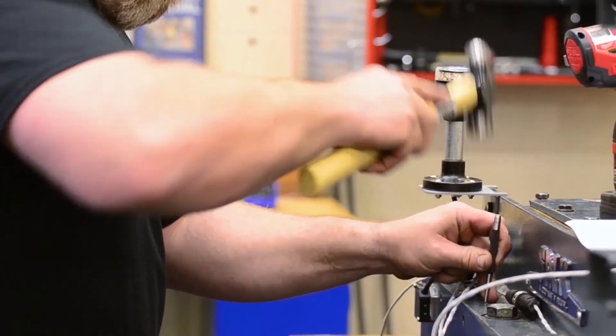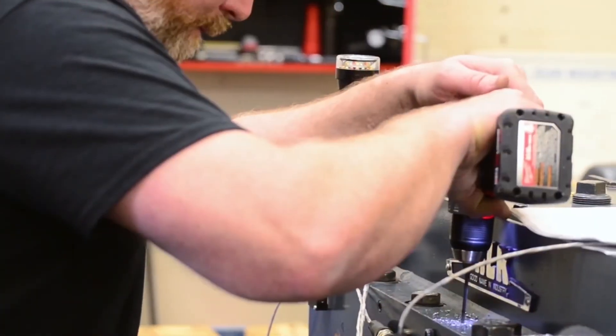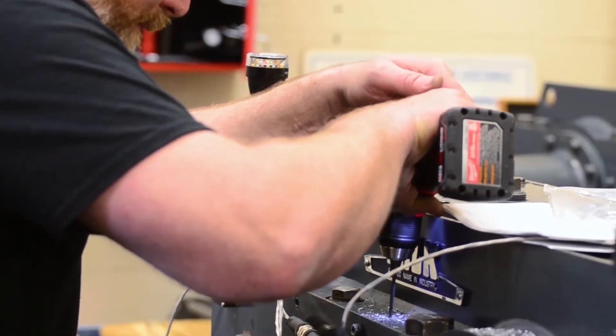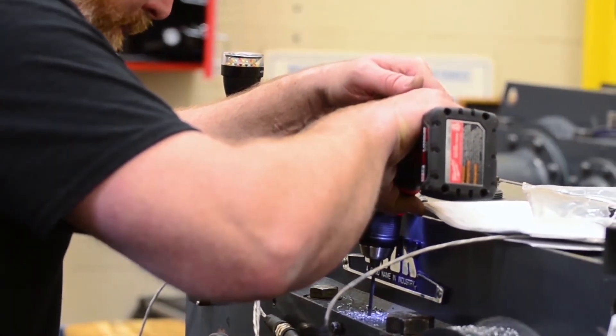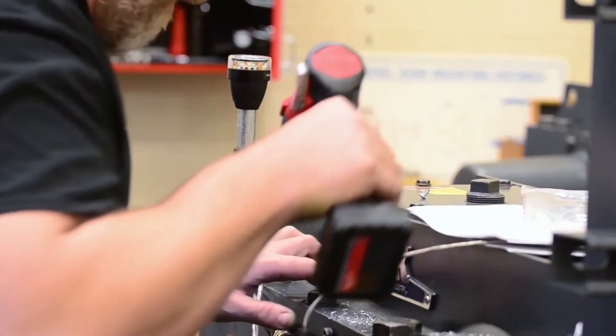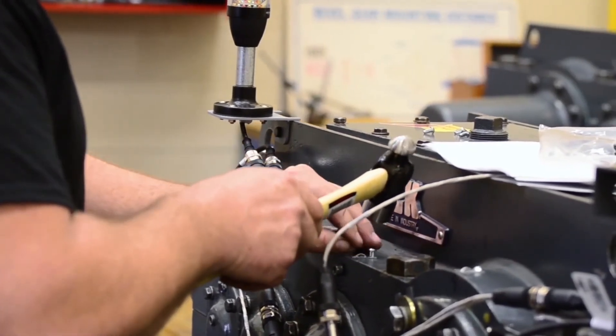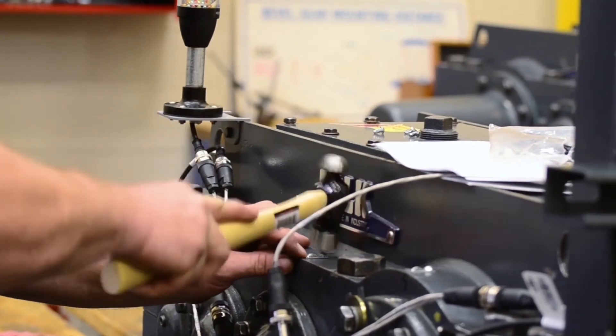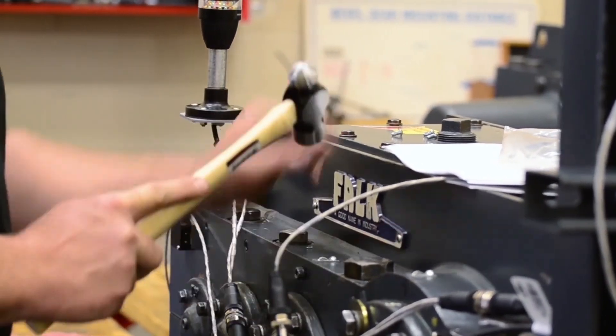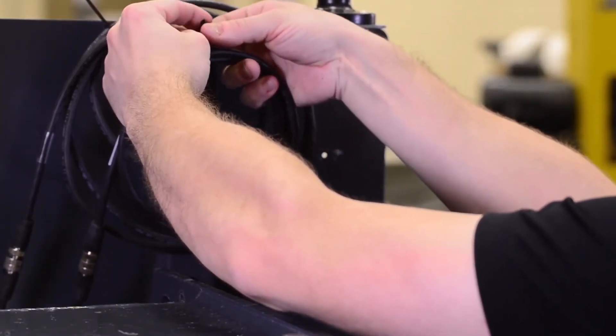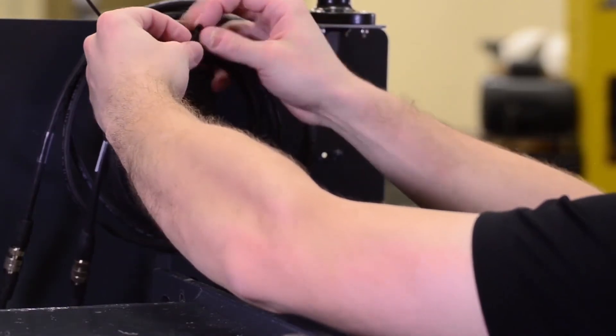Beginning with the furthest sensor and working your way back to the edge device, secure the cables with the provided cable mounts and ties. Drill holes for the cable mounts on the end or on the ledge where the split bolts are located. Using a number 27 drill bit, drill holes to a maximum depth of 0.14 inches and secure the cable mounts with a number 8 drive screw. Loop any excess cable neatly behind the edge device and use the cable ties to secure the cables to the unistrut.